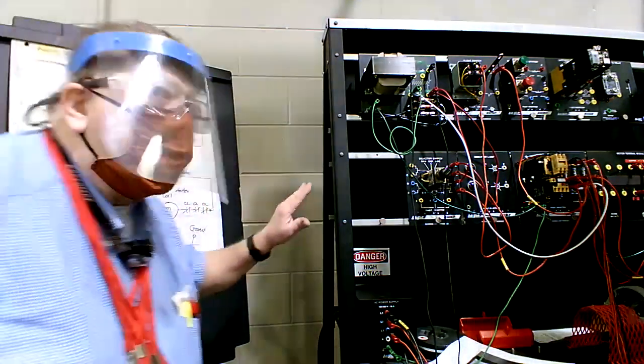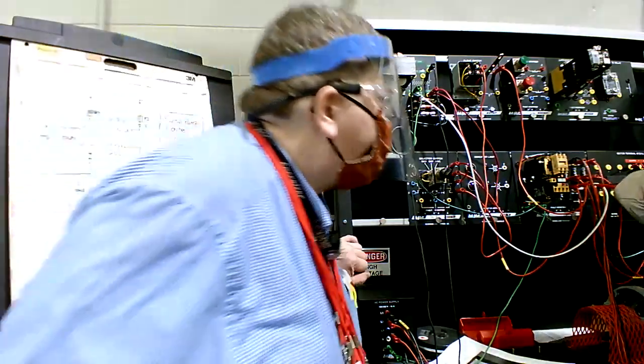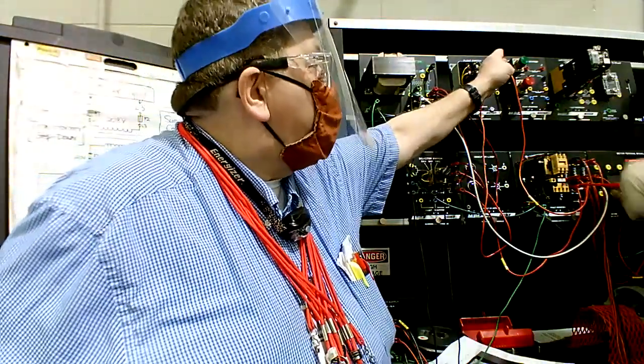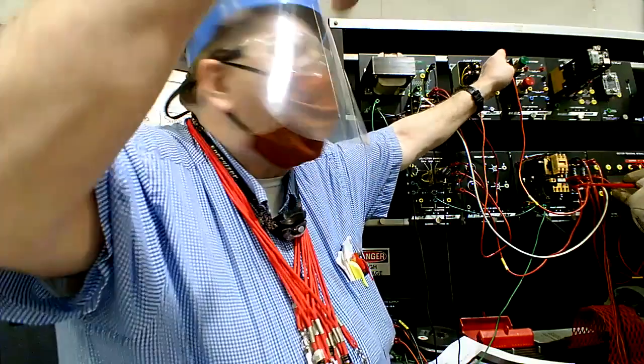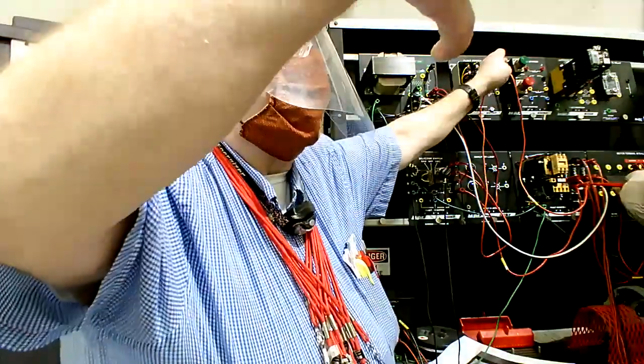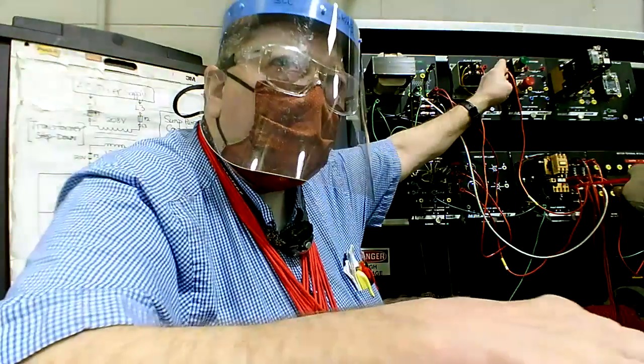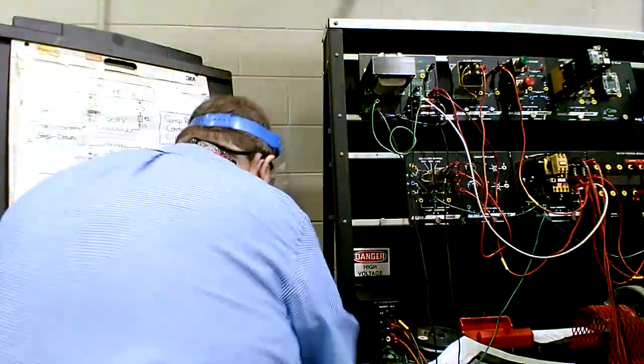Now listen, leave your leads on there and watch. When the float's up, you've got 120. Look, when the water goes down, you lose the 120, right? Now the water comes up again. It comes on, the pump runs and the water's high. When the water goes low, it cuts off. Now watch this. Watch this.